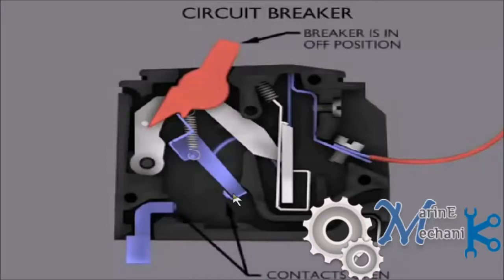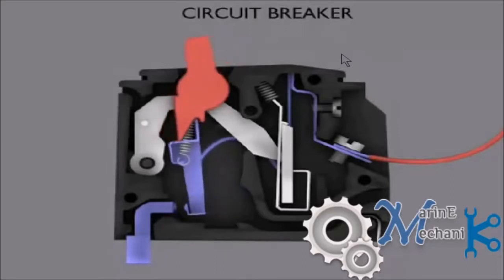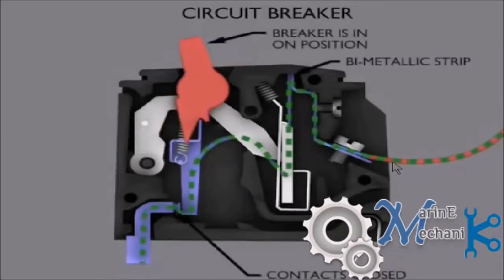Alright, so these contacts are open now, the breaker is in off position. Now it's on, the current starts to flow through the supply line, that's the red line. The current flows through this terminal, and here you have screwed it, so remember that it flows through this. If it's loose, then definitely there's going to be a problem with the circuit breaker, like arcing, or even the circuit breaker might trip. Any fault may occur over here. So through this it goes to this and enters the bimetallic strip.